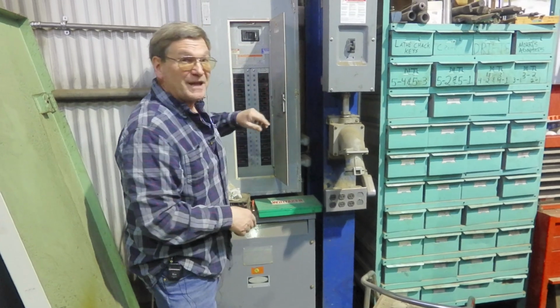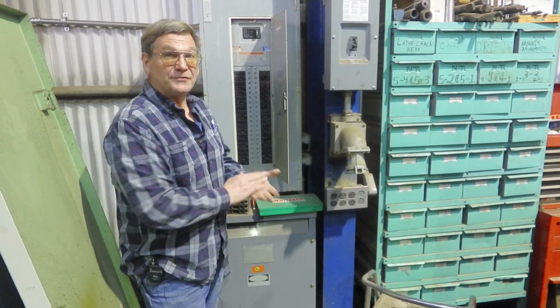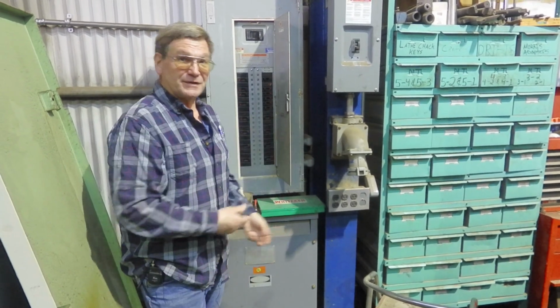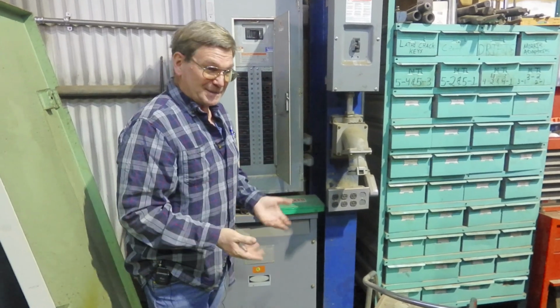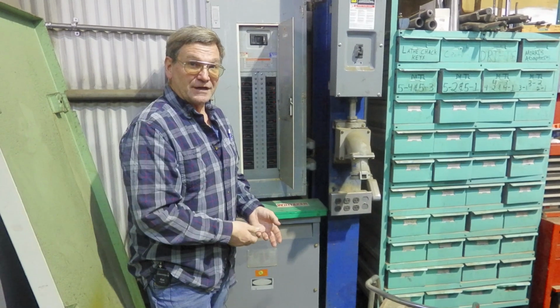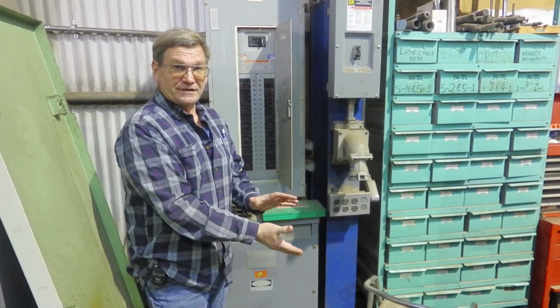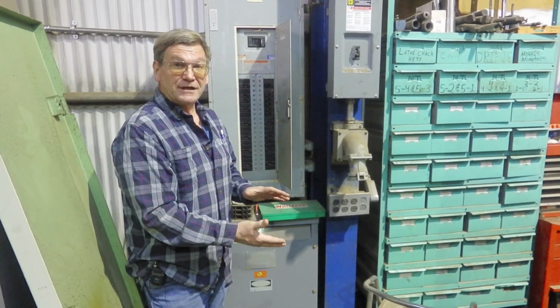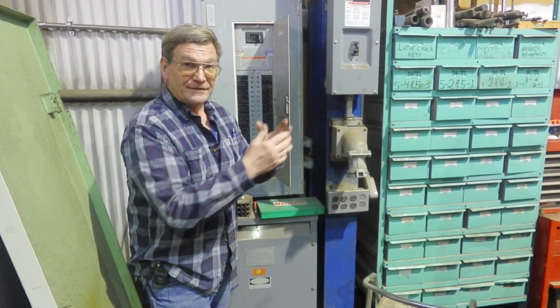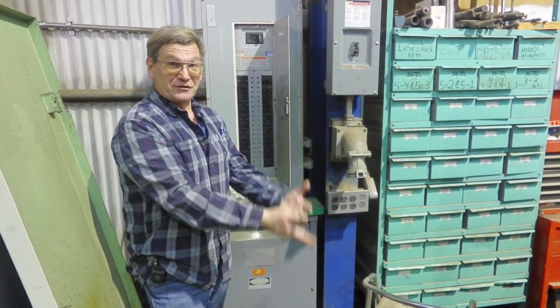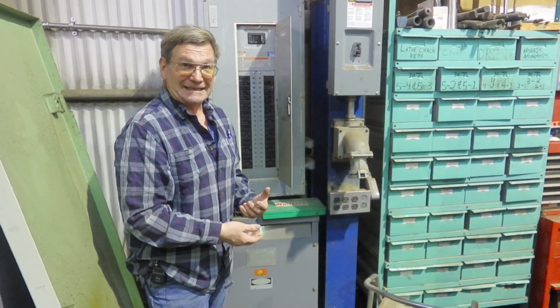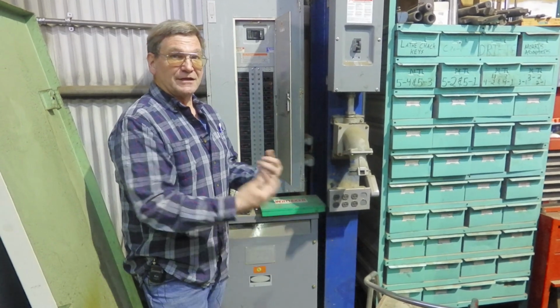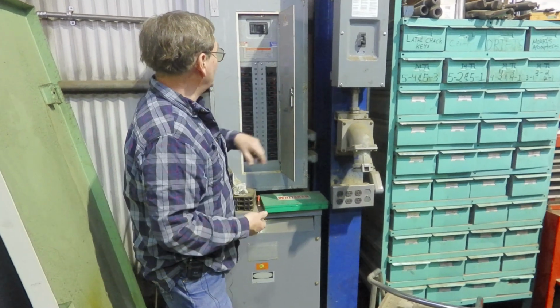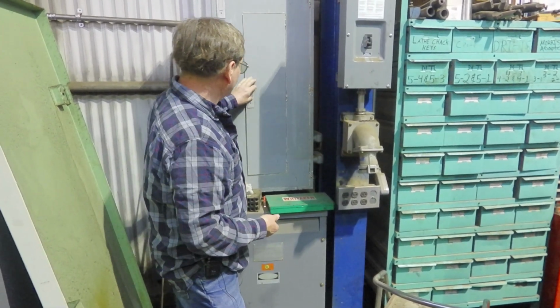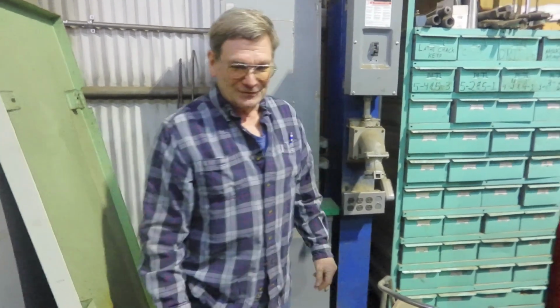You can set up a whole other main panel and get a whole lot more amperage available without spending a lot of money on a 480 to 380 volt transformer by taking an inexpensive surplus 480 to 208 transformer, and because it's only carrying part of the current, a 45, I think this was a 45 kilowatt transformer, and that's now 45 kilowatts at the 100 volts that you're using it to buck instead of 45 kilowatts spread over the 380. So it doesn't take as big of a transformer to carry a whole lot more current into your shop, and then that way we wired this whole sub panel that is 380 volt. So I don't know how unconfusing, or we'll make a little bit of a sketch, I guess, up here on the board.